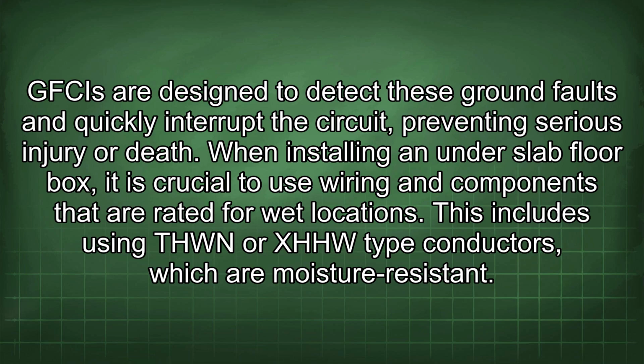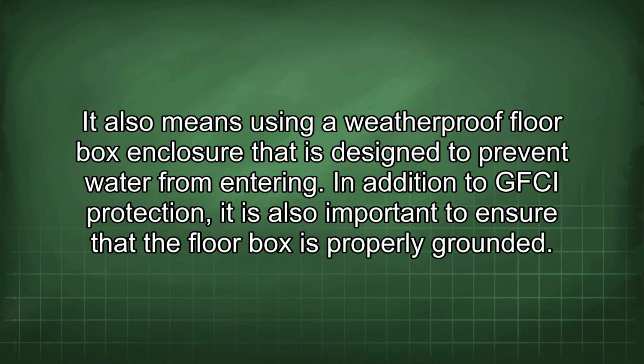When installing an under-slab floor box, it is crucial to use wiring and components that are rated for wet locations. This includes using THWN or XHHW type conductors, which are moisture resistant. It also means using a weatherproof floor box enclosure that is designed to prevent water from entering.